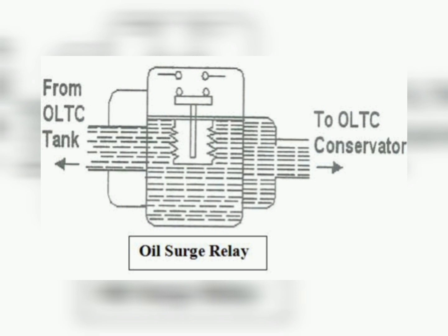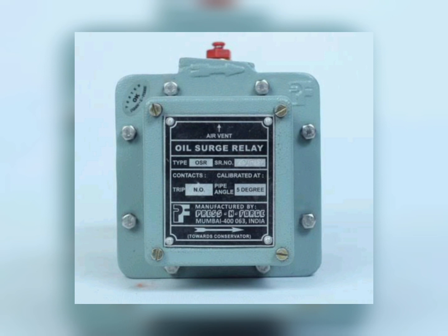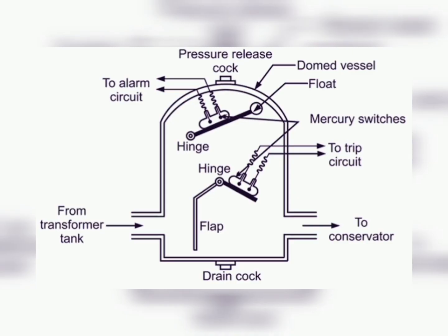Overall, the oil surge relay is an important protection device that helps ensure the safe and reliable operation of the transformer by protecting it from damage caused by oil surge. Additionally, another relay type is designed to detect gas or oil leaks within the transformer, as well as other internal faults that could damage it. When a fault is detected, the relay will trip and shut off the power to the transformer, preventing further damage. It is commonly used in large power transformers and is an important component of the transformer's protection system.